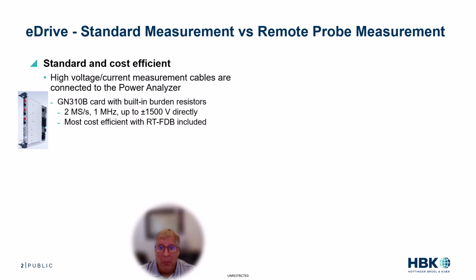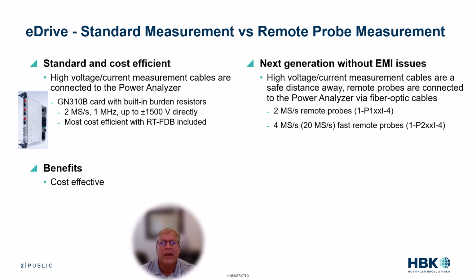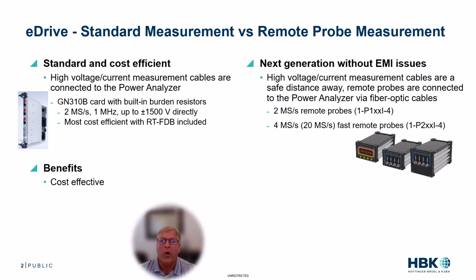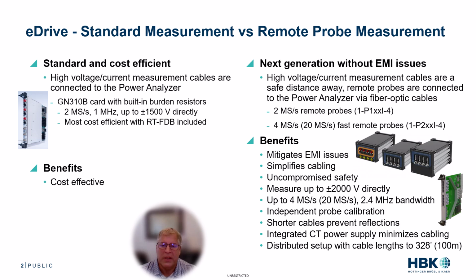However, to mitigate EMI issues and take advantage of all the numerous benefits in E-drive measurements, the next generation measurement method has high voltage and current cables a safe distance away from both the power analyzer and you, the user, by using remote probes connected to the power analyzer via fiber optic cables. Now, there are two variants of the remote probes, and we'll talk more about that in a moment. However, the many benefits include what you see here.